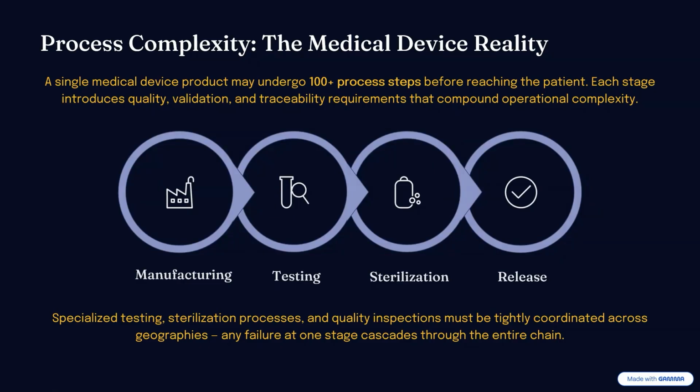So as far as medical device manufacturing is concerned, you have a different set of standards. We have a quality management standard, ISO 13485, which is different from the automotive one. We have different testing standards when you test a medical device. If it's an electromechanical device, you have the 60601 series. If it's mechanical, then you have another transport testing.